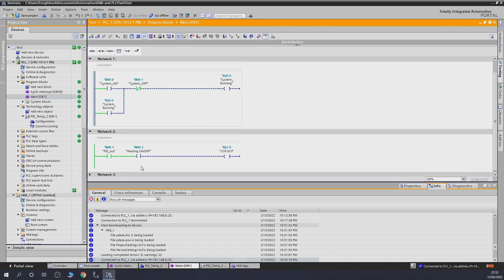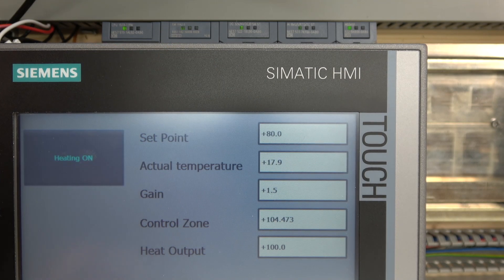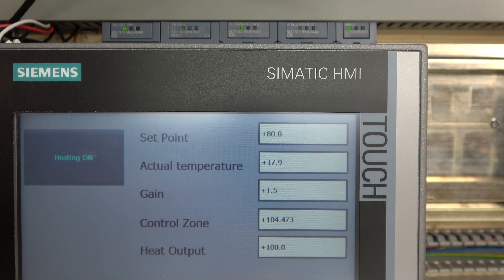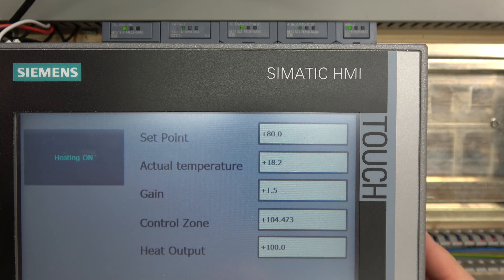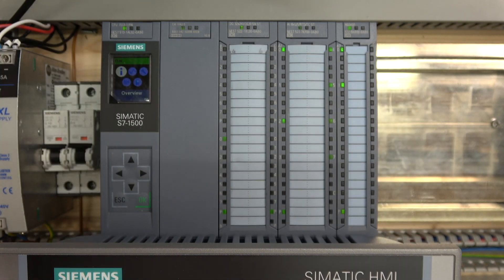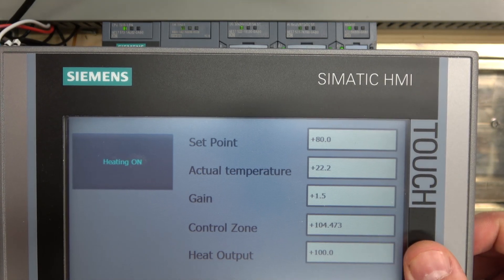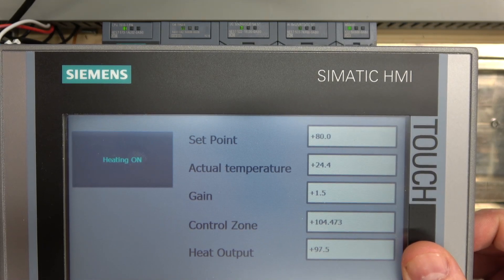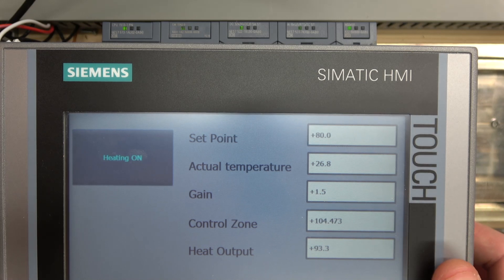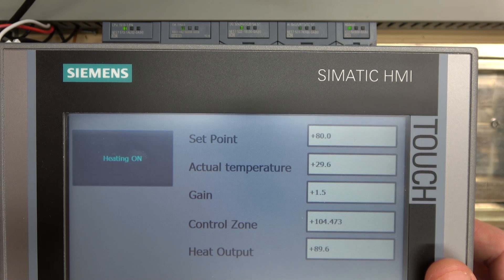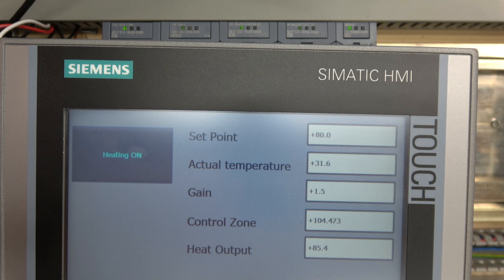Let's turn the heater on to demonstrate. You'll see in a minute that the heat output is at 100% — it was already on. Let's let it start heating up so we can see what's going on. The temperature is rising, the digital output is at 100%, and the heat output display on the HMI reflects that. Now you can see the controller is already starting to reduce the heat output, which is a little too early for my liking — that's why we need to retune it.